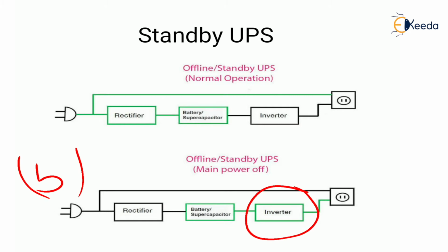Normally, the inverter is operating in the standby mode, keeping the batteries charged. And so, when the utility power goes out of specification, the inverter powers the load, drawing energy from the battery. This topology is called single conversion because the power is only being converted once, either AC to DC or DC to AC. So this is standby UPS or offline UPS.